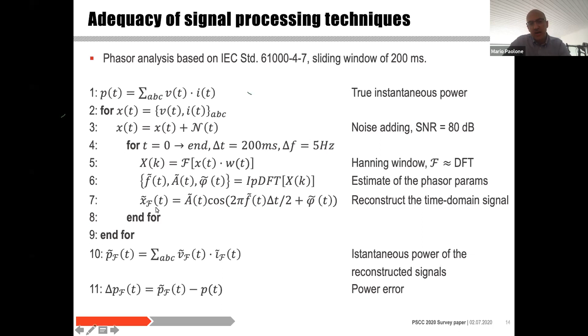Now, if we apply this simple algorithm to our two-bus model, where there is a frequency ramp of minus 5 Hertz per second, you end up with an error in the three-phase power of about 12 megawatts over 500 transmitted. If you do the same exercise when the voltage is experiencing an amplitude modulation at 5 Hertz with 10% amplitude depth, the error is way bigger. We are talking about 200 megawatt with spikes going above 300 megawatt, which is a pretty substantial error, as you can see.